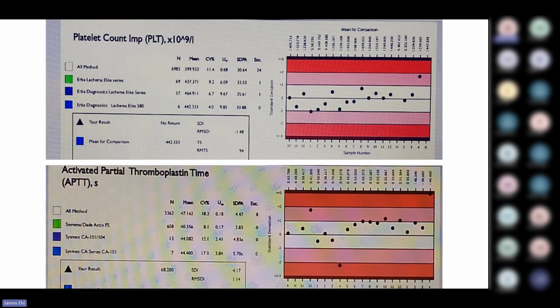But if you can maintain, and it takes a definite conscious act of reagent viability and in use of calibrator, equipment maintenance performed correctly and at the right time, weekly, daily, monthly, 2 monthly, 3 monthly, 6 monthly, yearly, as it is, you need to ensure that each of those maintenances are done correctly.